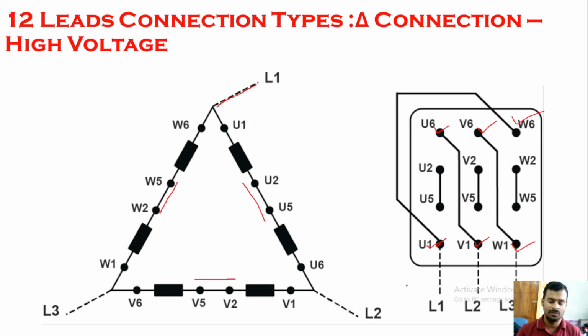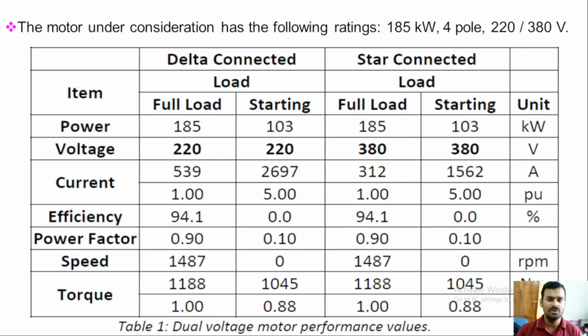So now let us see how the nameplate looks for this dual voltage motor and how the performance will be. You can observe here it is a 185 kilowatt, 4 pole, 220 and 380 volt motor. At 220 volt it will be connected in delta, and at 380 volt it will be connected in star. So that means for low voltage it should be connected in delta, and for high voltage it should be connected in star.